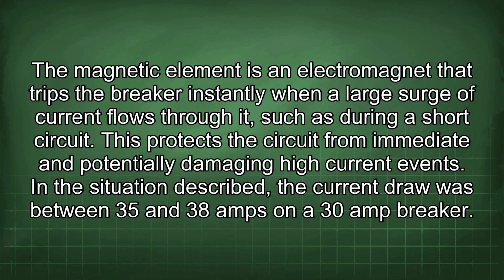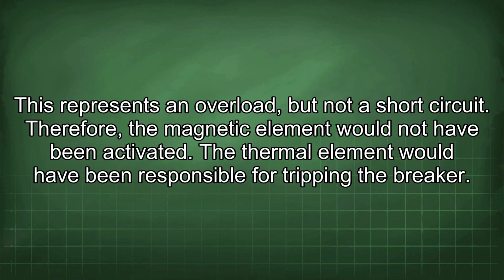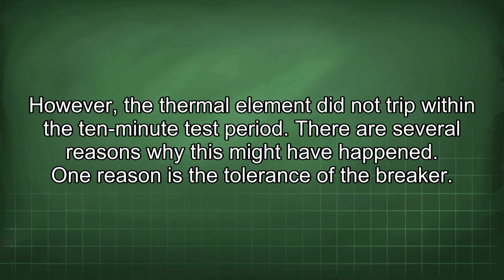In the situation described, the current draw was between 35 and 38 amps on a 30 amp breaker. This represents an overload, but not a short circuit. Therefore, the magnetic element would not have been activated. The thermal element would have been responsible for tripping the breaker. However, the thermal element did not trip within the 10-minute test period. There are several reasons why this might have happened.